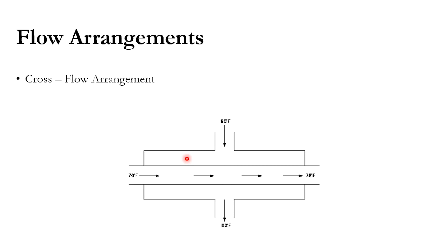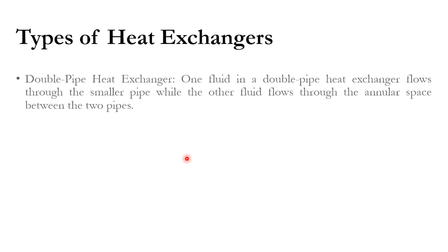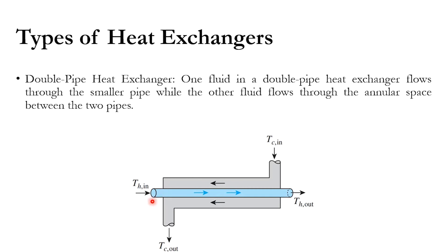The first type of heat exchanger we will discuss is the double pipe heat exchanger. In this design, one fluid flows through the inner smaller pipe — for example, the hot fluid enters at temperature Th_in and exits at Th_out — while the cold fluid flows through the annular space between the two pipes, entering at Tc_in and leaving at Tc_out. This is typically arranged in counter flow configuration.